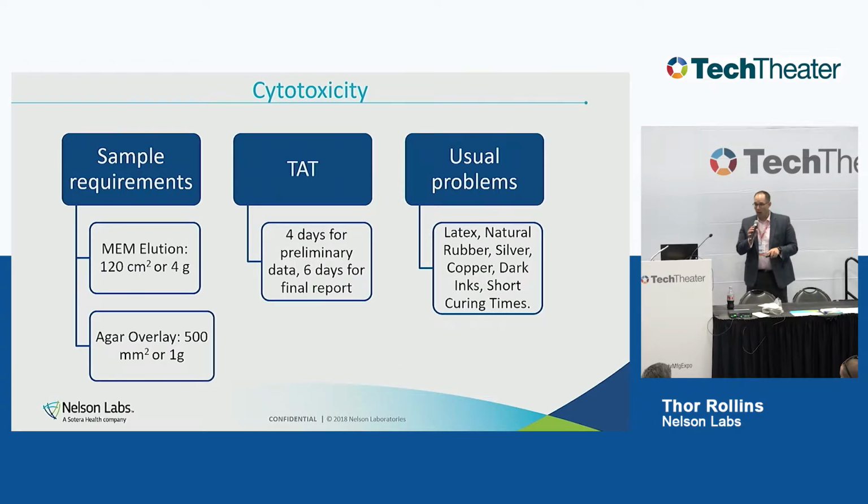Now that's great though, because this is by far the cheapest and quickest test we have. So it makes it great for screening, great for trying just to understand how a change may have impacted your device, things like that. But it also means that things will fail that aren't necessarily unsafe, okay? So I'm not going to get into failures right now because I don't have time, but if you ever fail a cytotox test, just call the lab up. We deal with test failures all the time. So we're going to be able to help you walk through those, understand it, evaluate it, get it through the FDA or notified bodies. But just remember, this one will fail, okay?